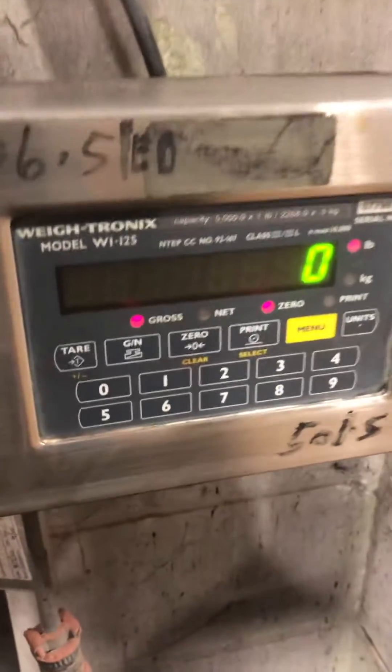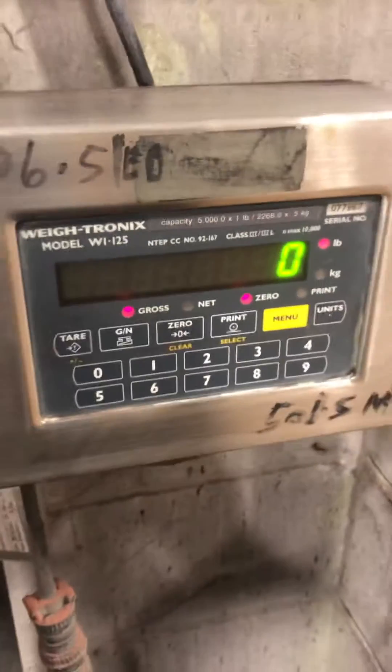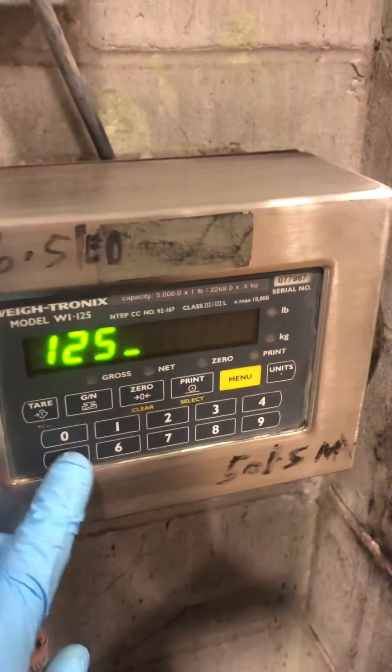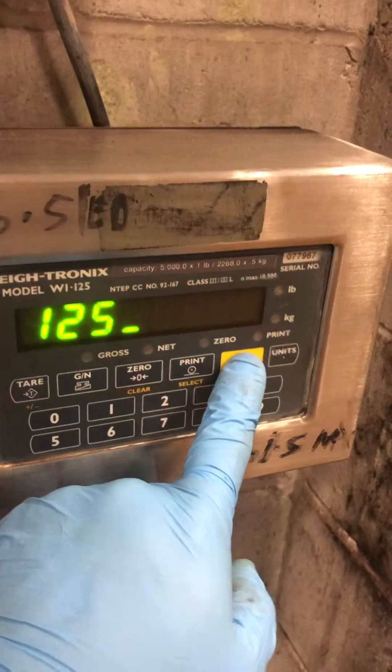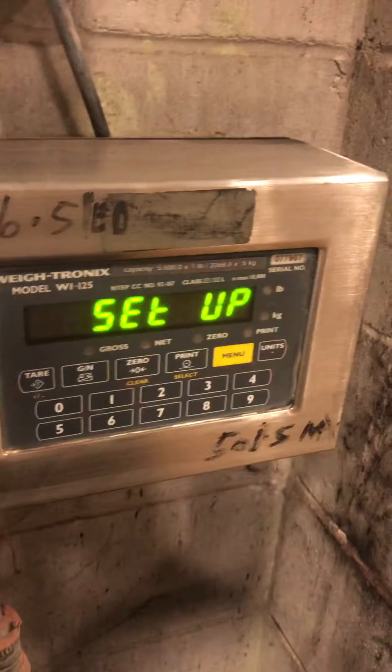This is our calibration adjustment of the Weigh-Tronix WI-125. First you're going to hit 1, 2, 5, and you're going to hold the menu until setup appears.